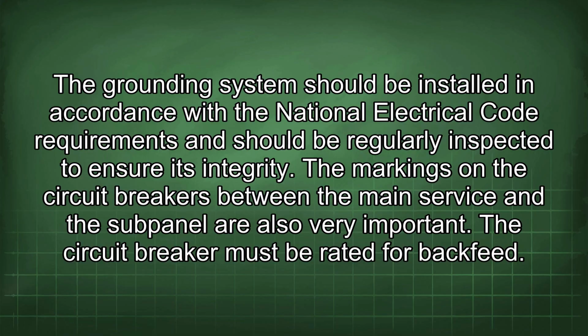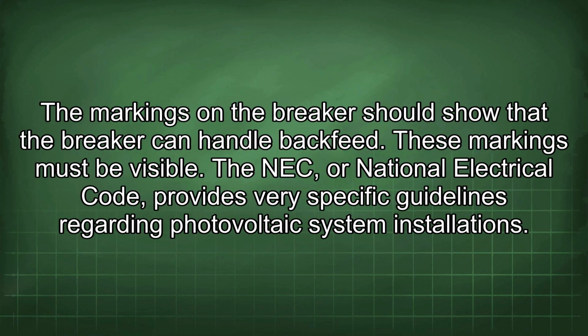ensure its integrity. The markings on the circuit breakers between the main service and the subpanel are also very important. The circuit breaker must be rated for backfeed. The markings on the breaker should show that the breaker can handle backfeed. These markings must be visible.